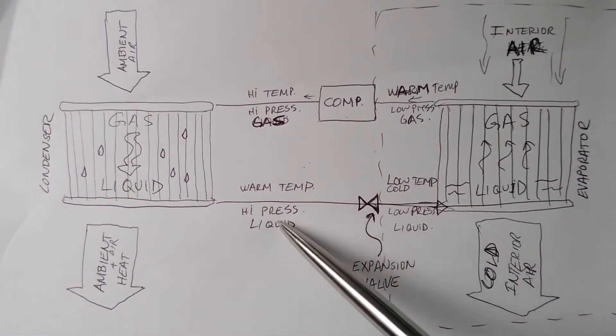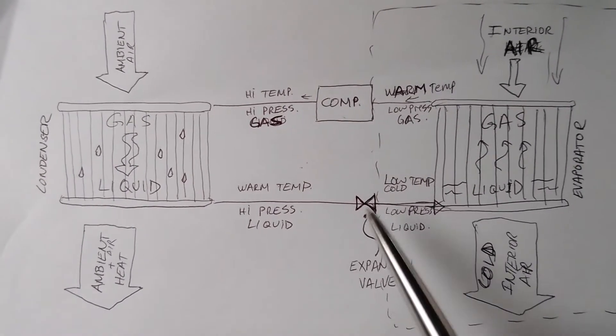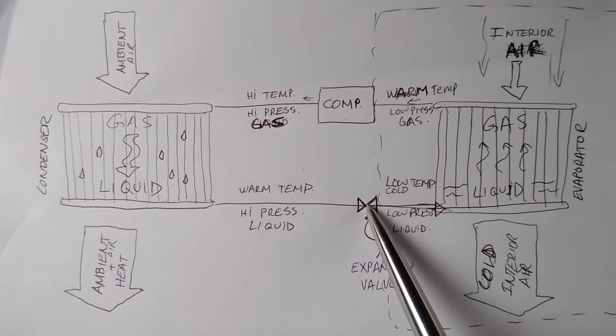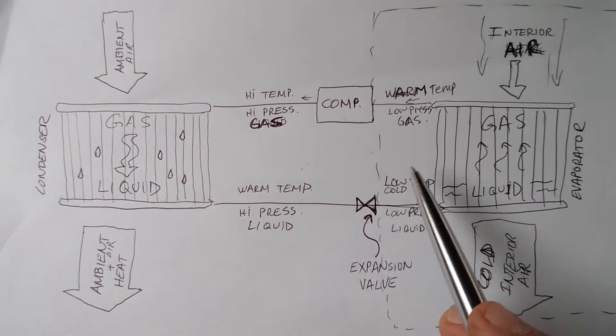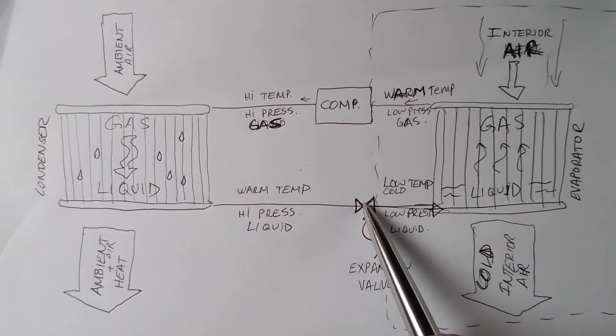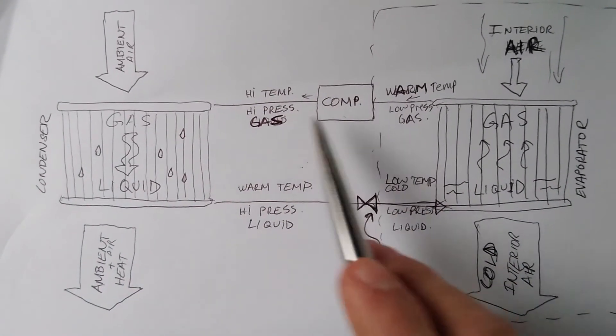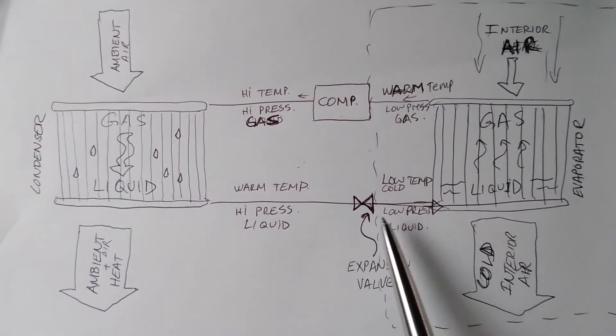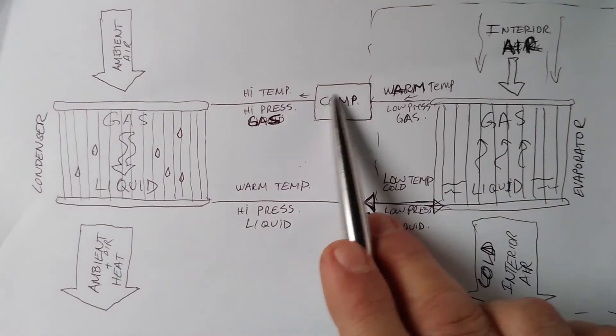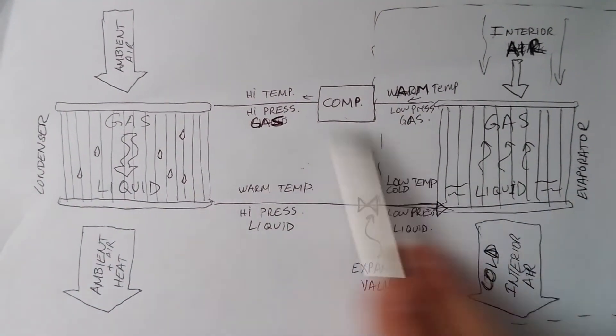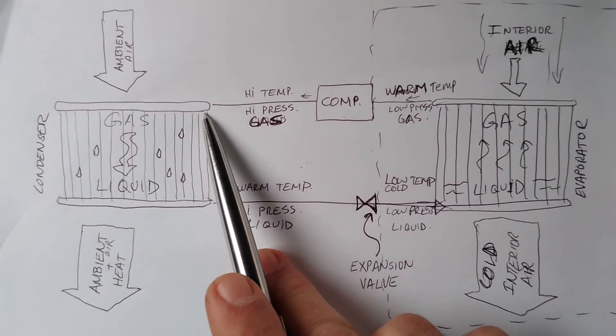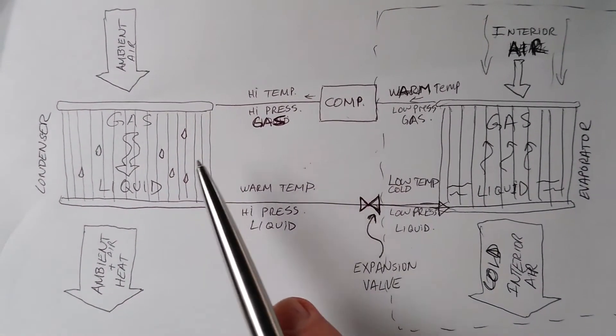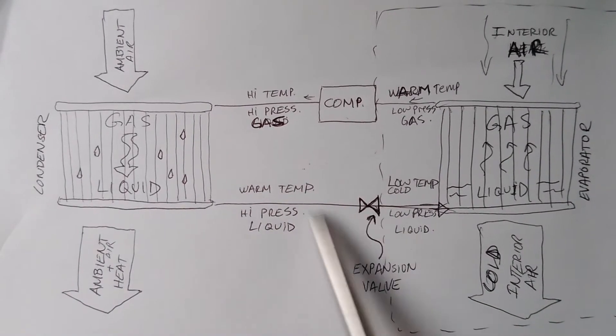Now you have a warm but cooler liquid still at high pressure, and you run it through an expansion valve. The expansion valve is a calibrated orifice — a small restricted hole — that provides enough restriction for the compressor to push up against and build up pressure on that side of the system. Without that restriction, the compressor would just circulate gas without raising pressure.